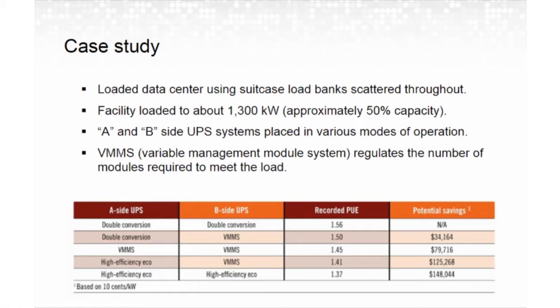some of the modules, because we were only at 50% and they're AB, so they're really only operating at 25%, the modules could be shut off and put in standby mode. And we did get some efficiency of dropping the PUE to 1.5, and that equated to about $34,000 of savings a year. The next mode was to put both sides in the VMMS mode. Again, we did see some reduction in the PUE. That equated to about $80,000 of potential savings.